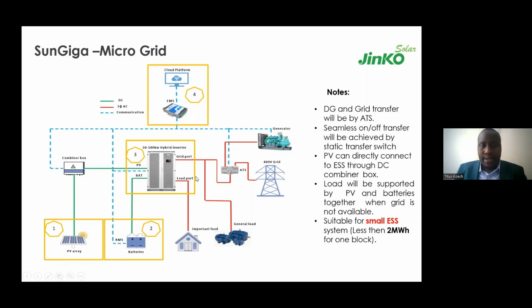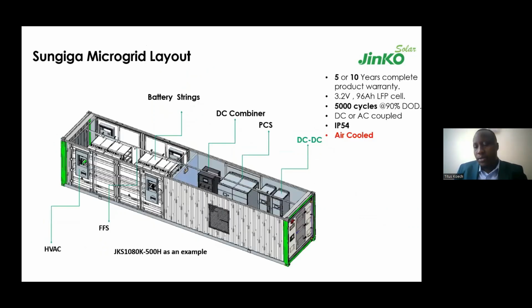Currently we're limited to less than 2 megawatt hours in a single block of 40-foot containers, but we can parallel up to 4 units of 40-foot containers, making it around 2 megawatts and 6.4 megawatt hours.